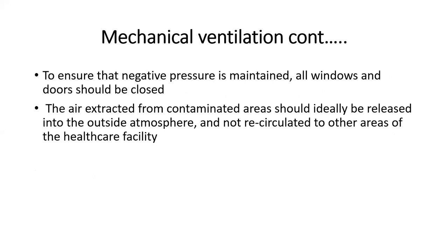All windows should be closed, and doors also should be closed. The air extracted from contaminated areas should ideally be released into the outside atmosphere and not recirculated in other areas of the healthcare system, which means the air which is in the room should not be circulated in other areas. It should go directly to the outside environment and not to any other wards or rooms.